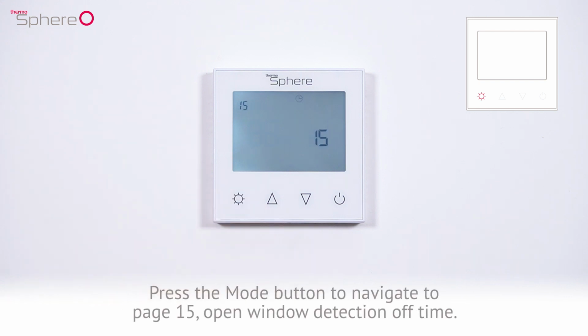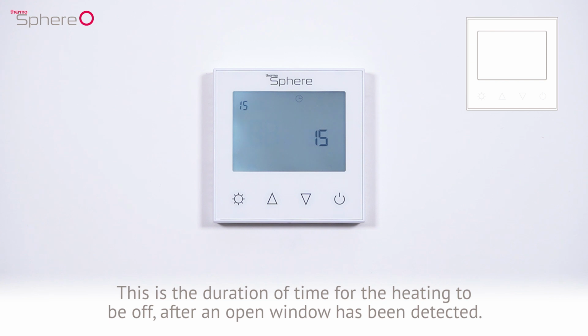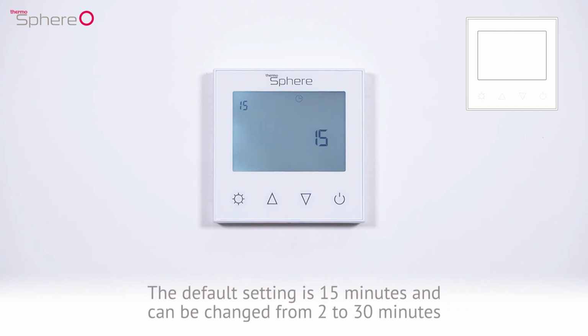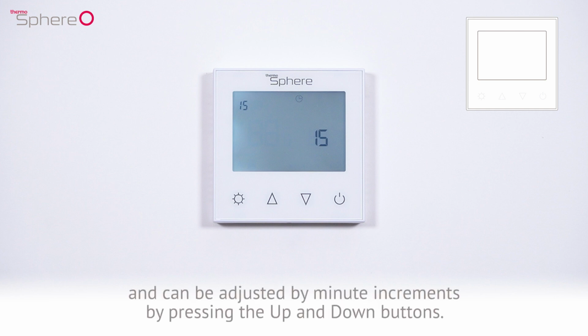Press the mode button to navigate to page 15, open window detection off time. This is the duration of time for the heating to be off after an open window has been detected. The default setting is 15 minutes and can be changed from 2 to 30 minutes and can be adjusted by minute increments by pressing the up and down buttons.